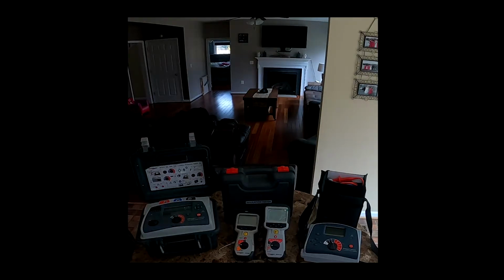for 1,000 volts. The difference between having a handheld 1,000 volt and the larger 5,000 volt is portability. For me to be able to run through low voltage equipment, 480 to 120, 208 transformers, for example, it's easier to carry around a handheld unit. The larger ones aren't difficult to carry around, but they're a little more cumbersome, and you're typically carrying tools. So the larger 5,000 volt Meggers, the difference between these two is this is larger because, one, it has the rechargeable battery. This one is all self-included.